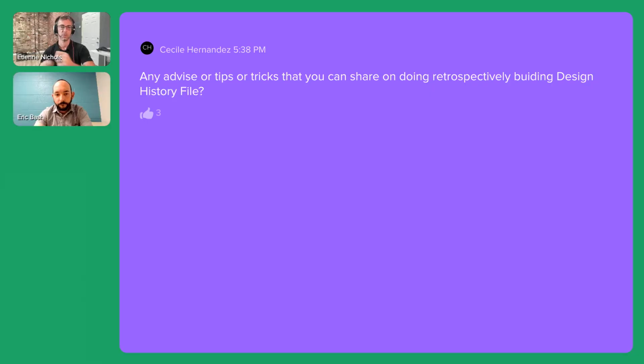Any advice or tips or tricks that you can share on doing retrospective building of the design history file? Well, avoid it if at all possible. You want to be building your design history file as you go, for all the reasons that we just discussed. That said, you kind of have to go back through and act as though you're doing the project from scratch, except you already have this thing. And you're kind of reverse engineering it and redoing the design history file as you go through that reverse engineering process. This will not be a value-add activity in terms of making a better product. All it's really doing is making sure that you have that design history file for either your next product, for changes to this product, and so forth.